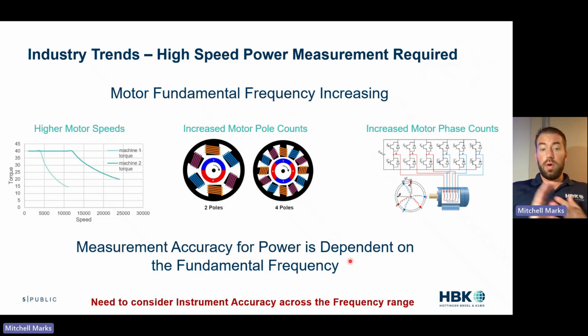For those of you who don't know, measurement accuracy for electrical power is dependent on fundamental frequency. And actually, this accuracy typically gets lower as the fundamental goes higher. So it's quite an interesting phenomenon, especially when you start looking at filters and all kinds of other behavior of measurement equipment. So when you go to select an instrument, specifically for power, you really need to consider the instrument accuracy across the frequency range.